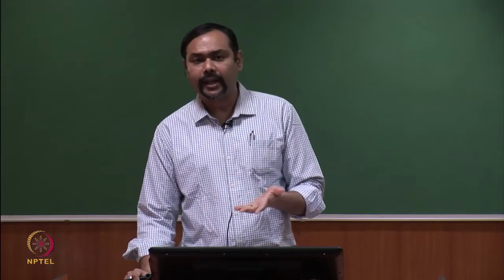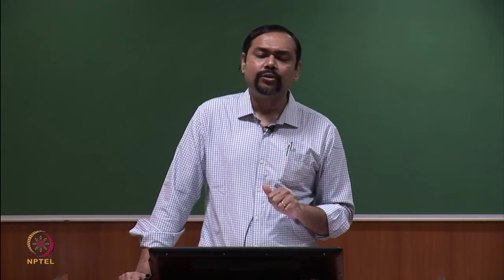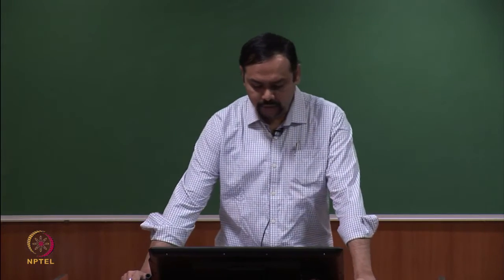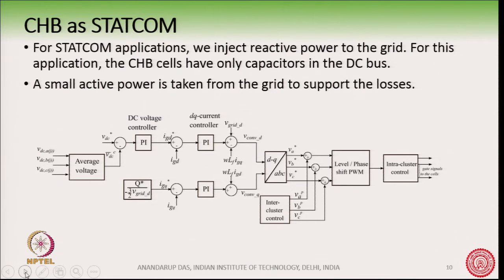It is a voltage source converter which injects reactive power into the grid. It can also support active power, but in this case we are talking about the very traditional STATCOM which is used exclusively for reactive power compensation. In this case, because we are asking only for reactive power from the STATCOM, we have only capacitors in the DC bus. We are not using any fixed DC bus which is fed from any DC power supply.